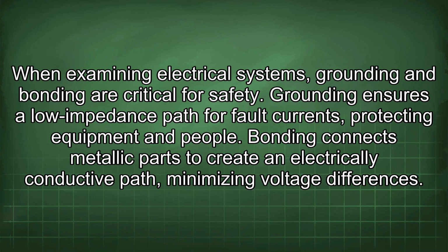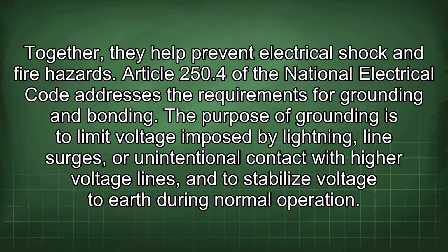When examining electrical systems, grounding and bonding are critical for safety. Grounding ensures a low impedance path for fault currents, protecting equipment and people. Bonding connects metallic parts to create an electrically conductive path, minimizing voltage differences. Together, they help prevent electrical shock and fire hazards. Article 250.4 of the National Electrical Code addresses the requirements for grounding and bonding.